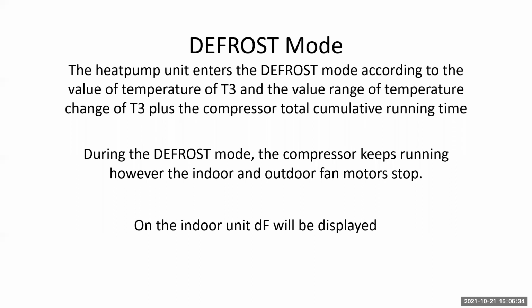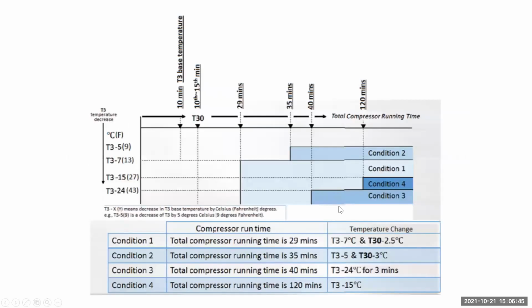During the defrost mode, the compressor keeps running. However, the indoor and outdoor fan motors stop. And most of your indoor units that have a display on them are going to read DF for defrost.